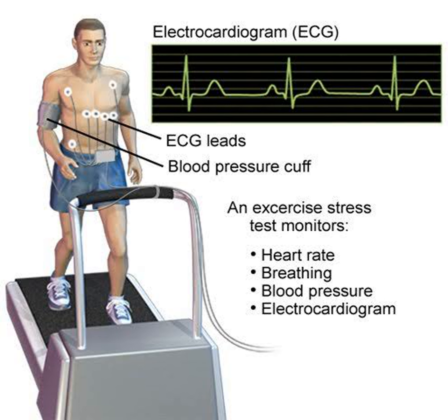Sixth one is TMT, specifically designed for monitoring heart activity while a patient exercises. These treadmills are not your typical gym equipment. They are medical grade devices that are integrated with ECG recording systems, helping doctors to diagnose coronary artery disease.